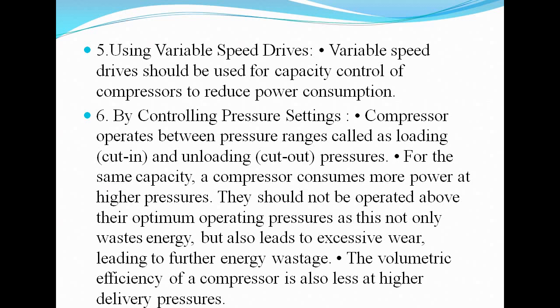And finally, by controlling pressure settings, the compressor operates between pressure ranges called loading, that is cut in, and unloading, that is cut out pressures. For the same capacity, a compressor consumes more power at higher pressures.